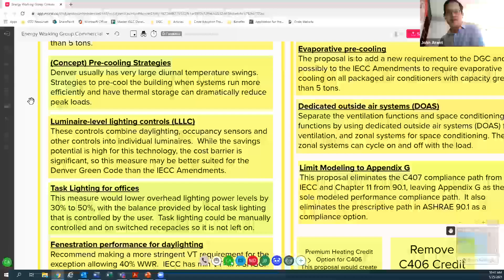Luminaire-level lighting controls combine daylighting, occupancy sensors, and other controls at individual luminaires. It has high savings potential but also carries some cost. The mitigating factor between this one and the next, task lighting, is that lighting power levels continue to drop in codes through increased use and efficacy of LED lighting, expected to reach around 150 lumens per watt or higher, which reduces the potential for these. I think offices are a good potential case, since you can reduce overhead lighting power levels by 30% or greater and just have user-controlled task lighting at the local desk, achieving real savings there.